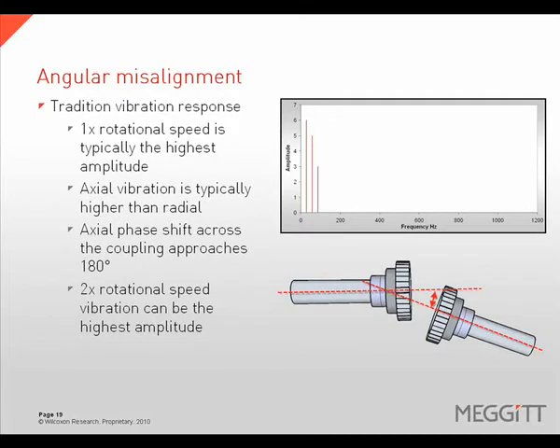Angular misalignment is characterized as having a higher 1 times rotational speed vibration, with the highest amplitudes often in the axial direction. The phase shift across the coupling should occur in the axial direction, and the analyst must consider the orientation of the transducer when collecting axial phase readings. While 1 times is the most common response to angular misalignment, it is not uncommon to find a 2 times vibration being highest in amplitude, making it difficult to distinguish from offset misalignment based on spectral data alone.